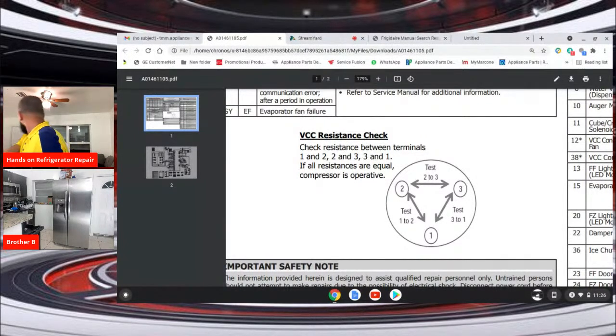This is your compressor terminals, apologies. It's telling you to check resistance between terminals 1 and 2, here's 1, here's 2, 2 to 3, and 3 to 1. If all resistances are equal, the compressor is operative.